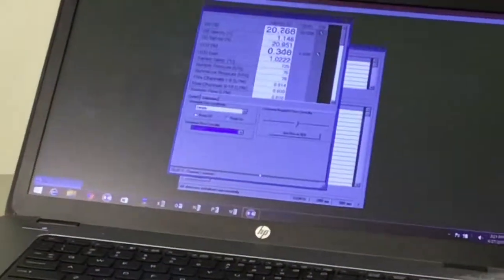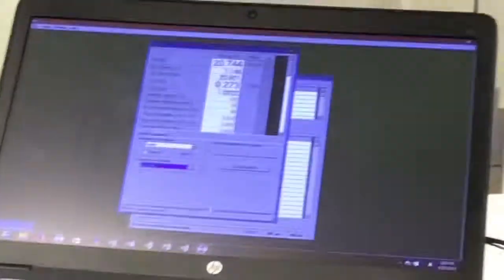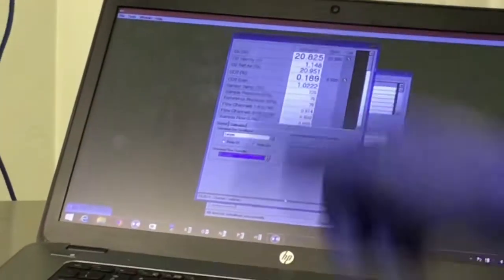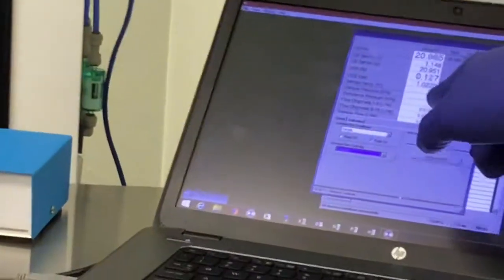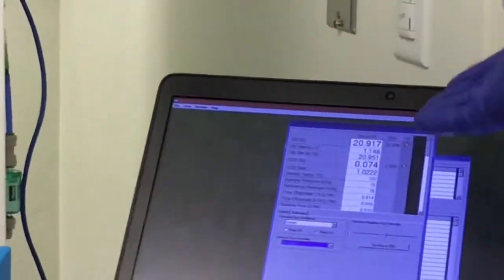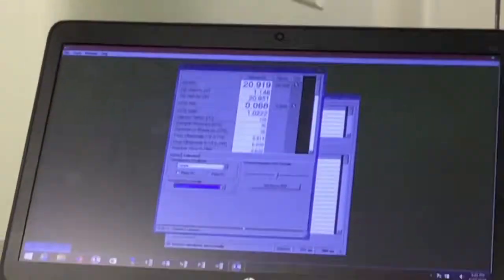So, again, now that I plug that back into the cage, which has room air inside, what should I expect? The CO2 level to go down and the O2 level to go up, to about 20.9 for room air. CO2 depends on how many people are here. If we shut these 2 doors, I promise you we will reach 0.1 quickly, with only us in here. But with these doors open, we have more air coming from the outside: 0.7, 0.07, 0.06.